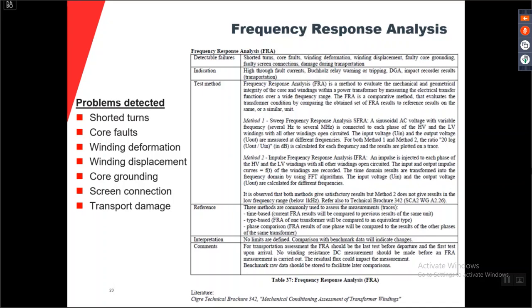While the impulse frequency response analysis is basically much quicker, because what you do is you send a quick pulse into the transformer, and then you record the response, and from that you do an FFT algorithm. So you do a fast Fourier transform algorithm, and by that you can calculate the frequency response. The SFRA takes a little bit longer compared to the impulse frequency response, but the accuracy at the lower frequencies is much better for the SFRA, while the impulse frequency response gives actually very, very similar results at the higher frequencies.